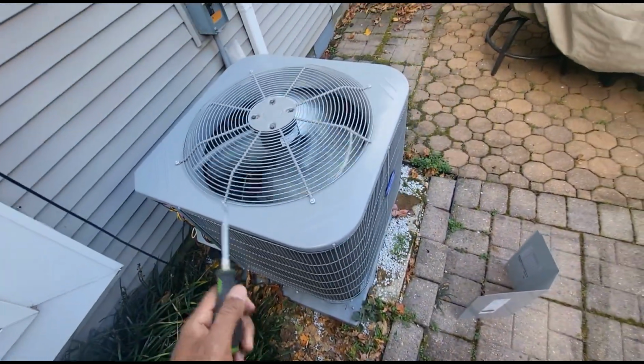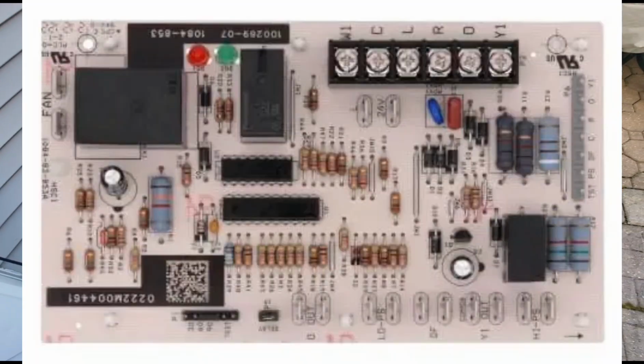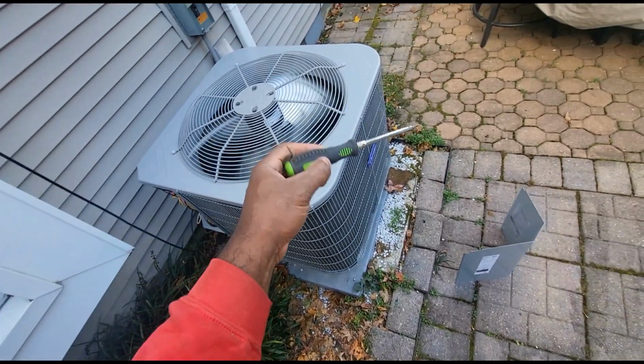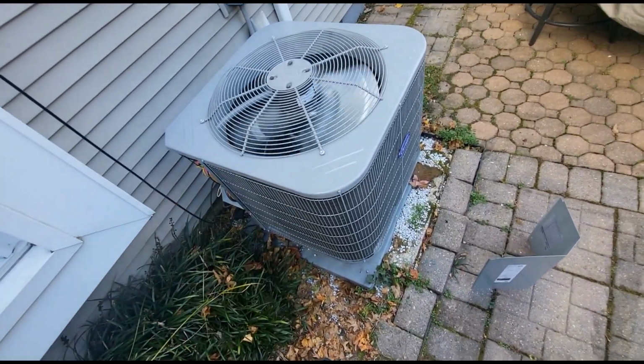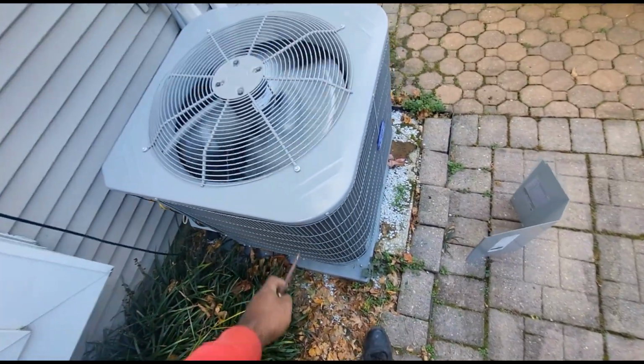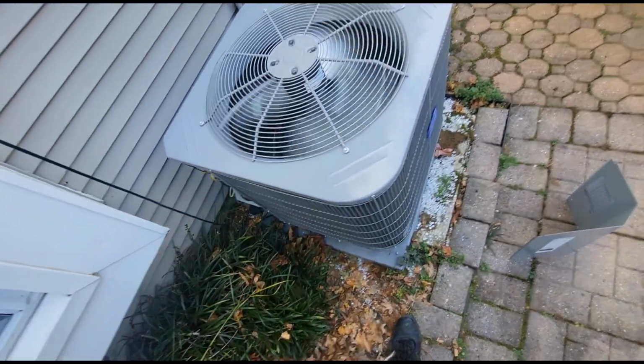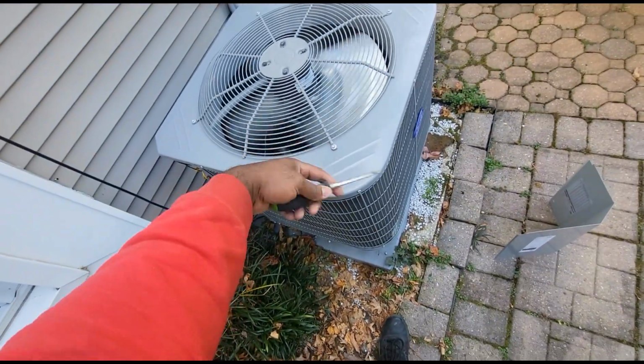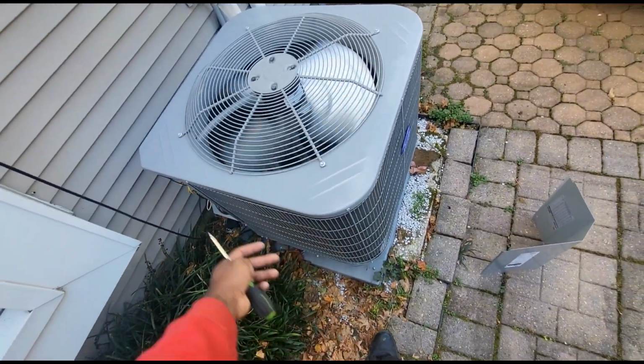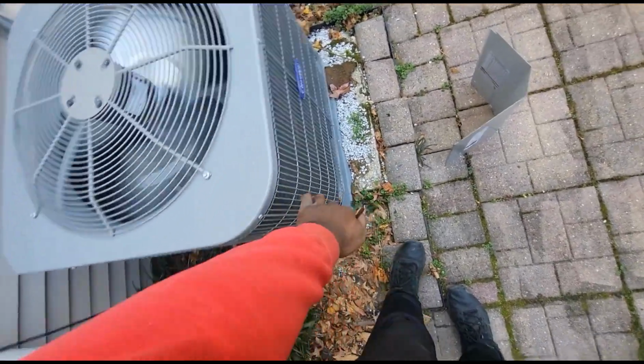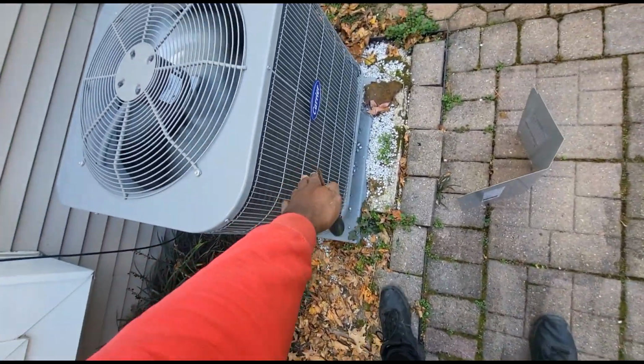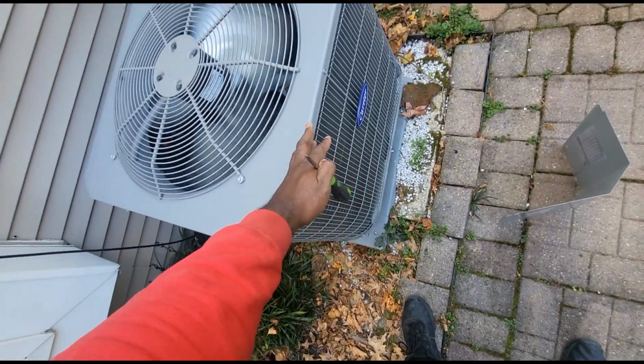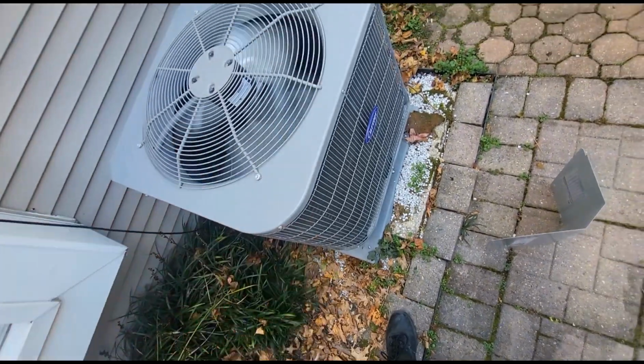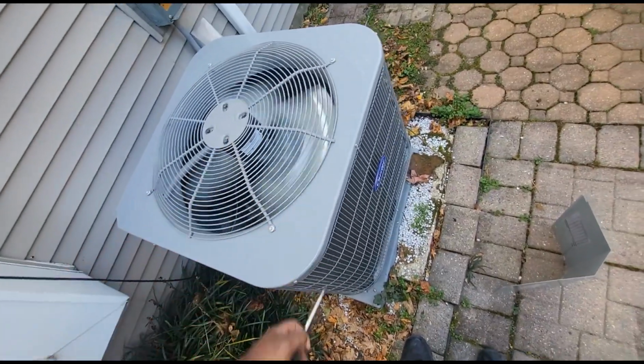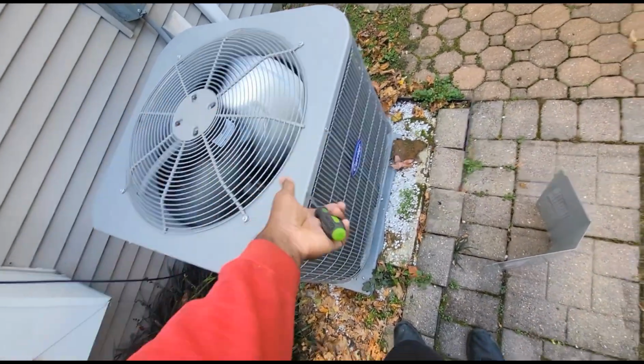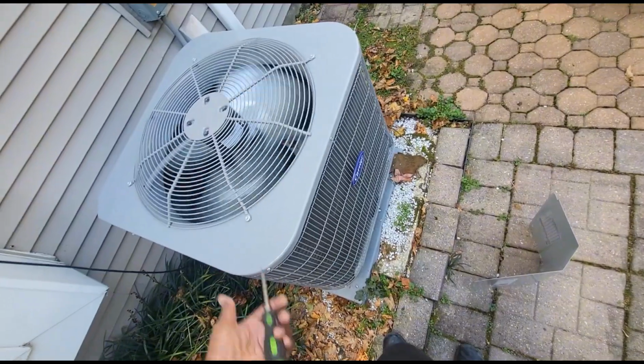On every heat pump maintenance, regardless of the age, you always want to test your defrost board. If I force the defrost and the defrost didn't engage, at that point I would recommend replacing my defrost sensor and the board. Reason being, if the coil temperature gets below 35 or 32 degrees and the defrost doesn't engage, now instead of having 1 or 2 small ice spots on the coil, if the majority of this coil freezes up, it could stop your fan motor from working, and now you're going to have a burnt fan motor to replace on top of potentially damaging the coil and/or the compressor.